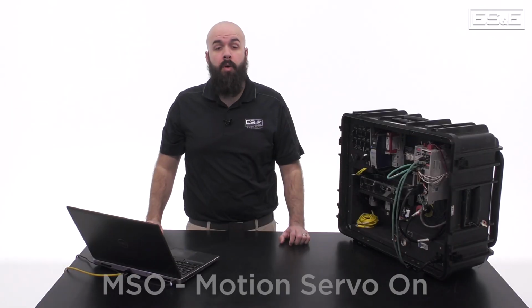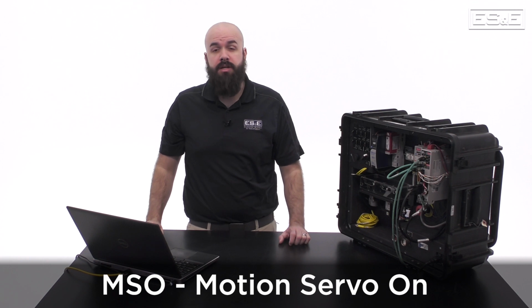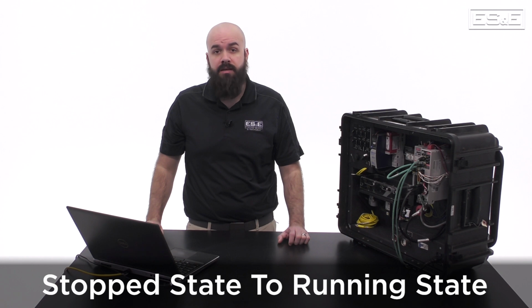The MSO, or Motion Servo On instruction, is the integrated motion instruction that is used to engage the position control loop for a servo. By executing this instruction, the axis will transition from a stopped state to a running state and will maintain the commanded position as closely as possible. Let's take a look at the different components of the instruction.